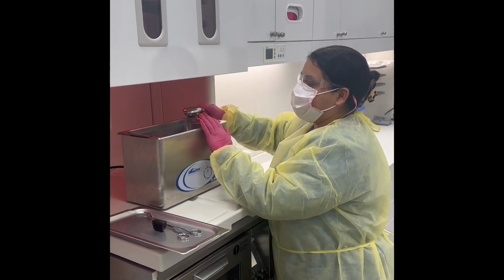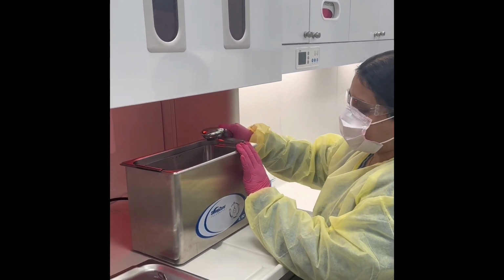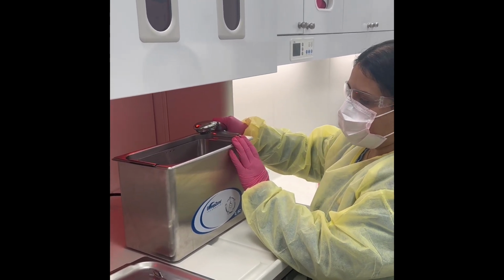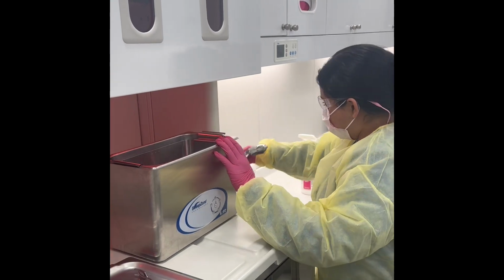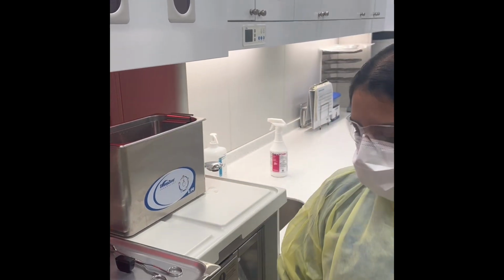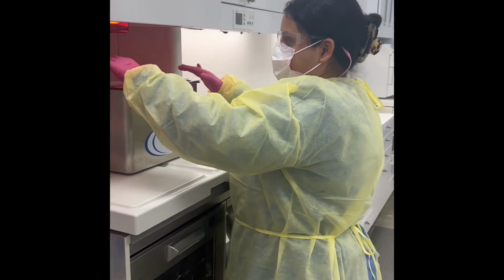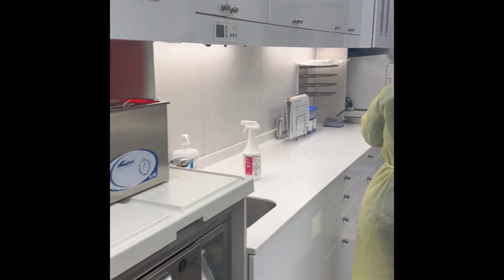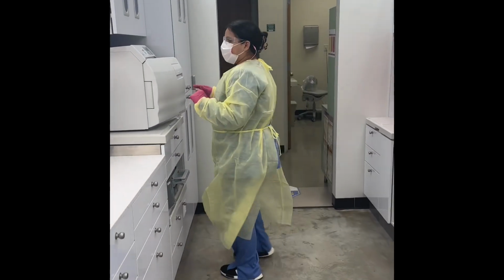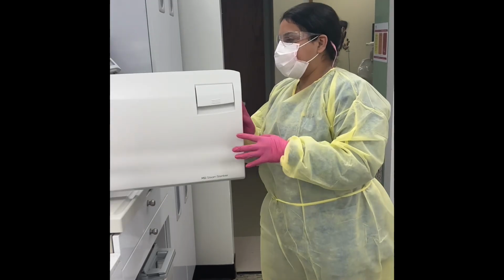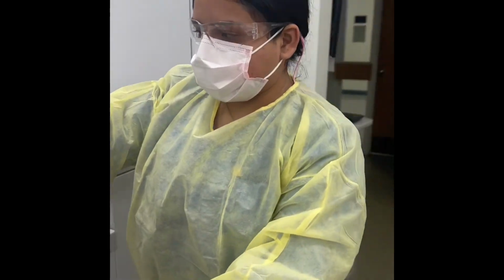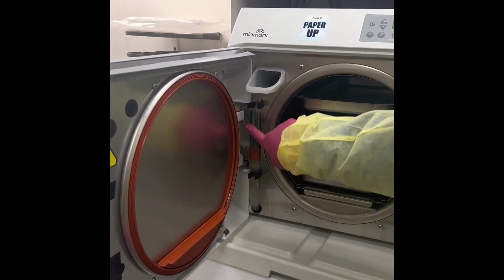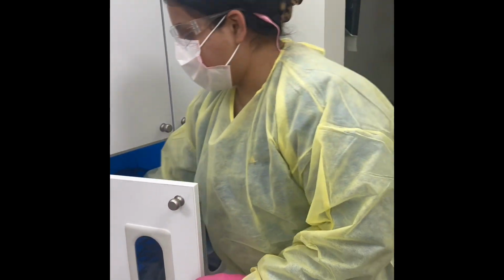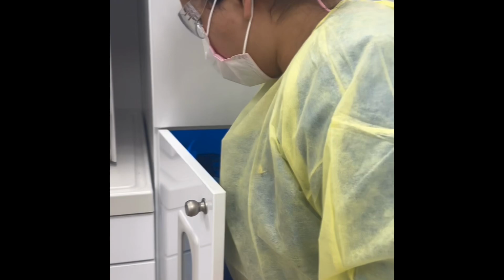Then you would fill up the ultrasonic to the appropriate water levels using distilled water. This is done daily, as water is drained every night or when visibly soiled. Next, we would move on to the autoclave. Check water levels. Make sure the water reaches the green line. If water does not reach the green line, add water.